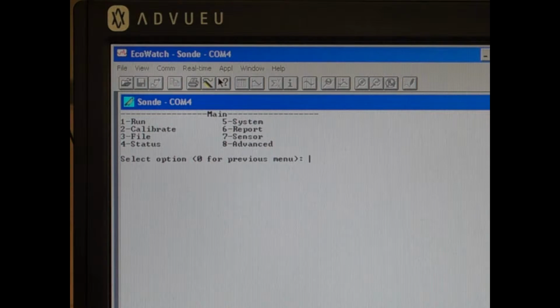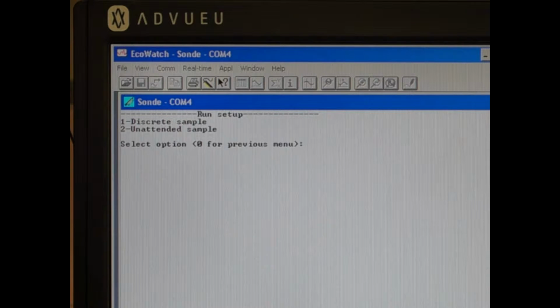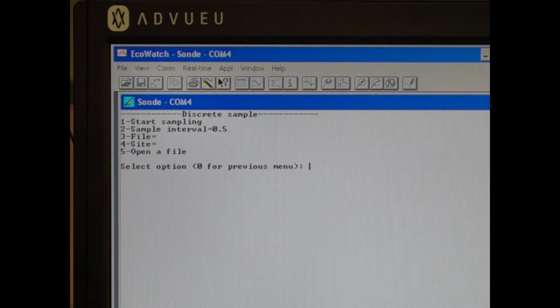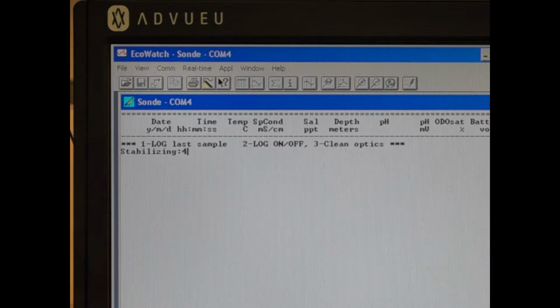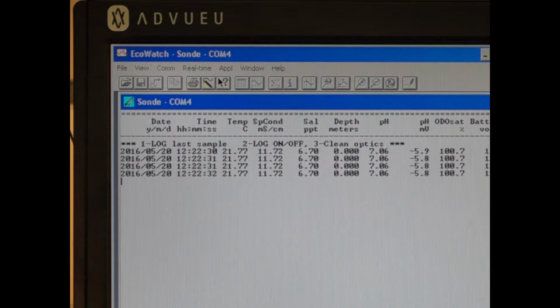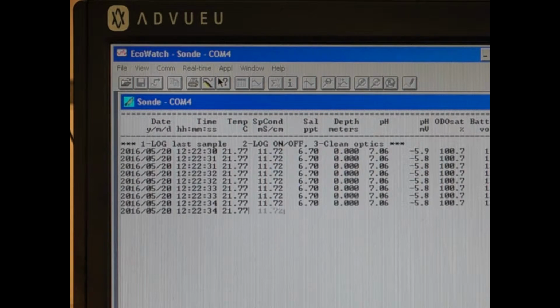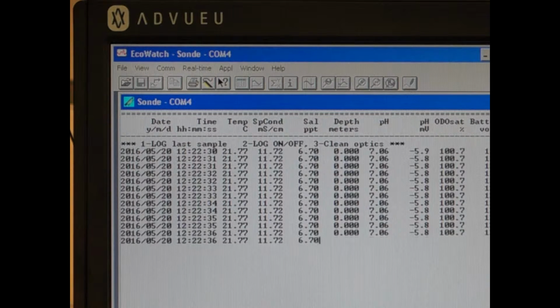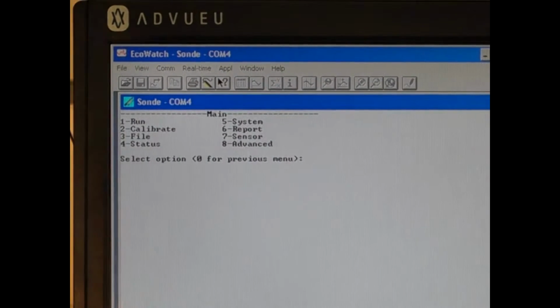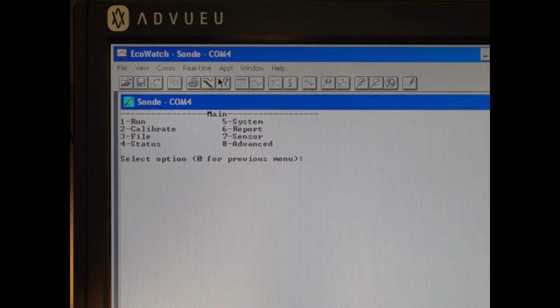So before calibrating the pH sensor, we need to actually discover what the temperature is of the solution. So we go to Run, Discrete Sample, and start sampling. So right now the temperature is 21.7. We write that down on the calibration sheet. So now we're ready to calibrate the pH sensor finally.